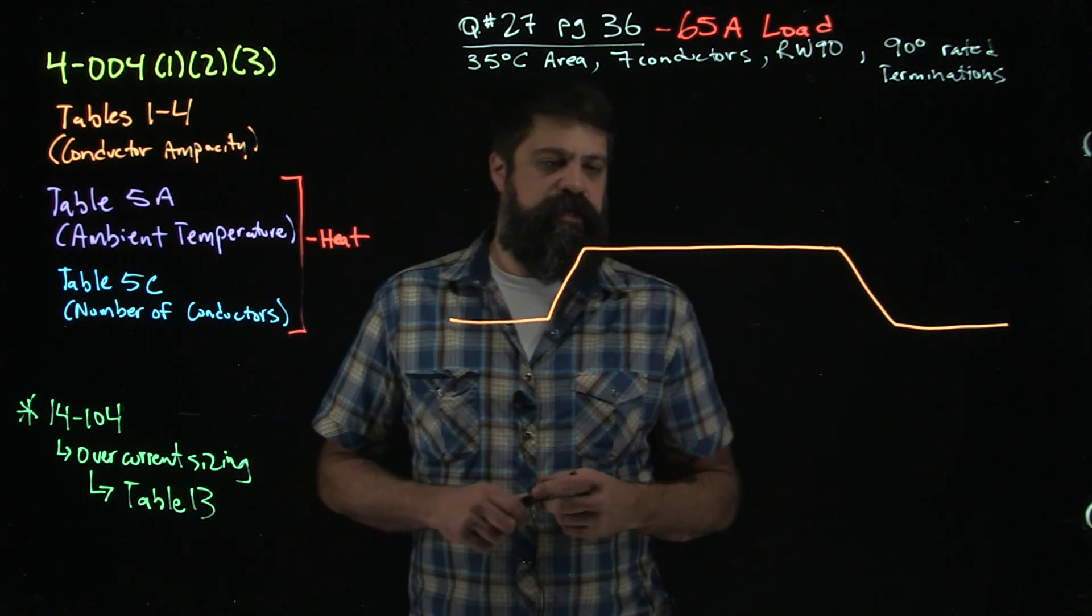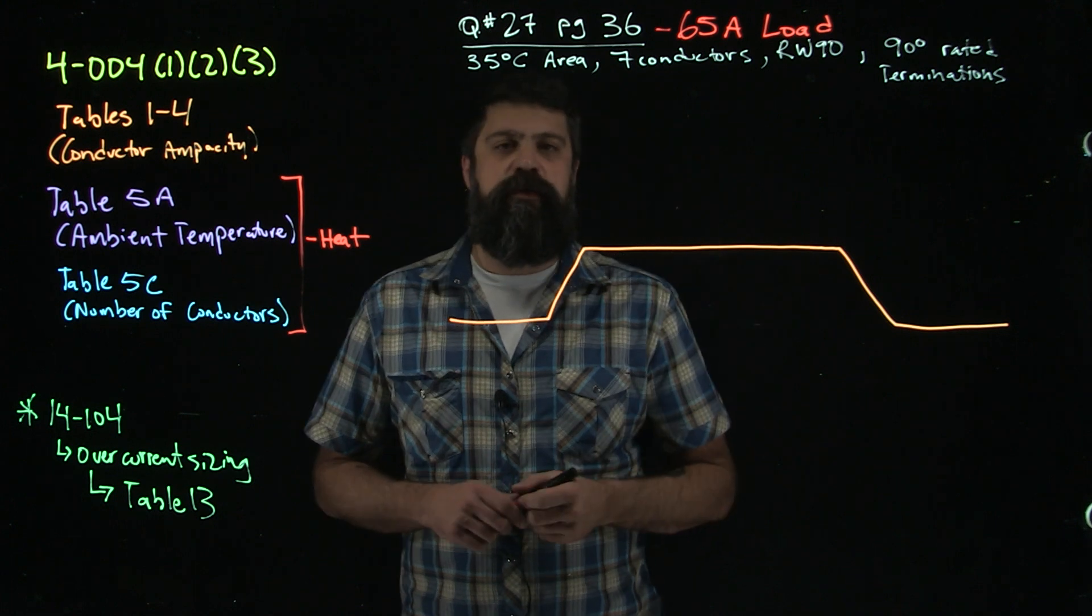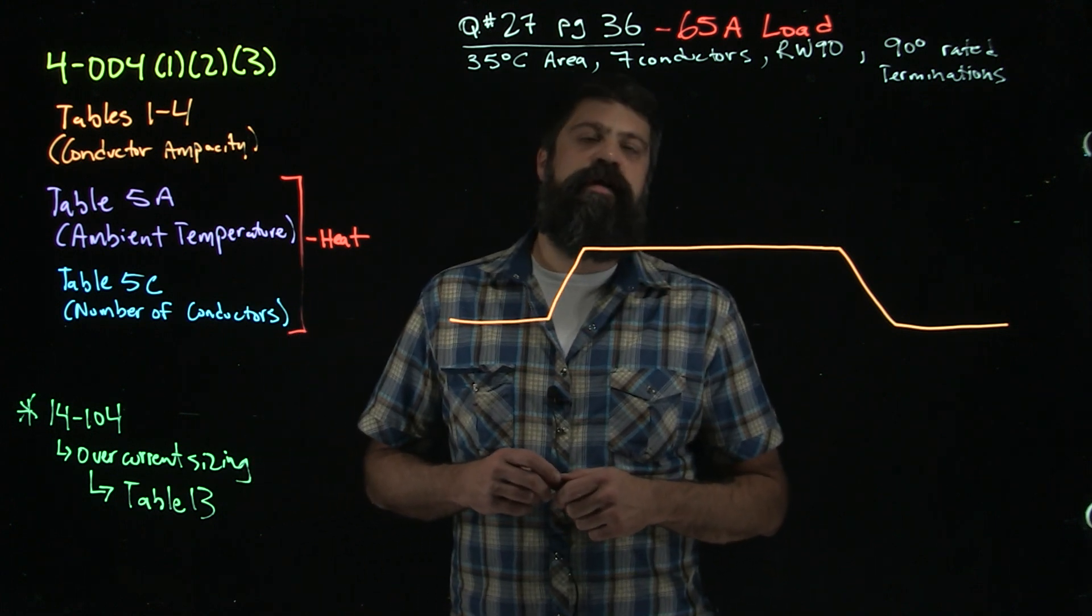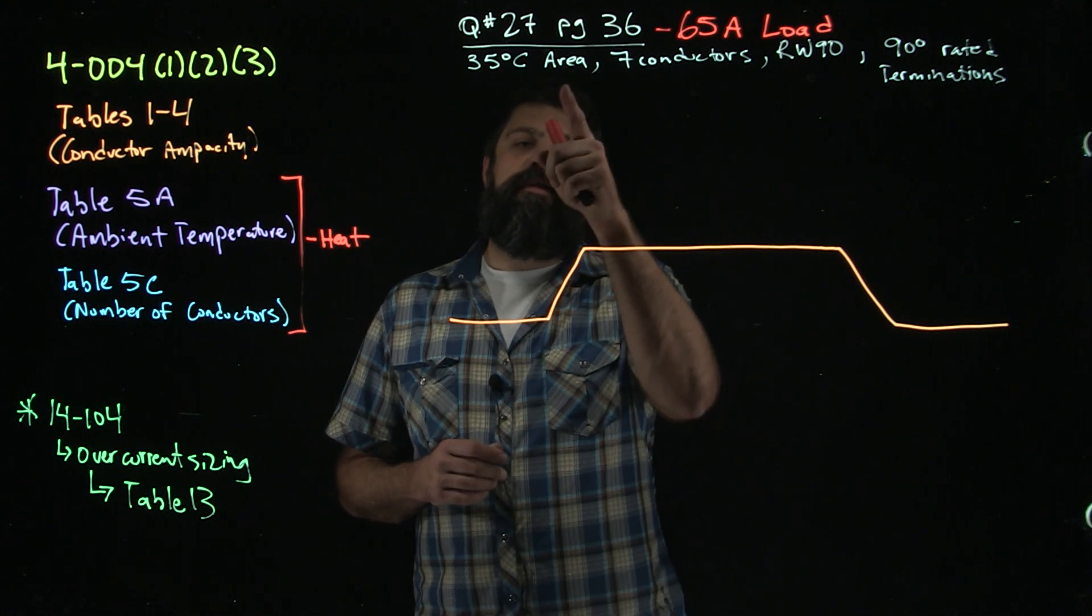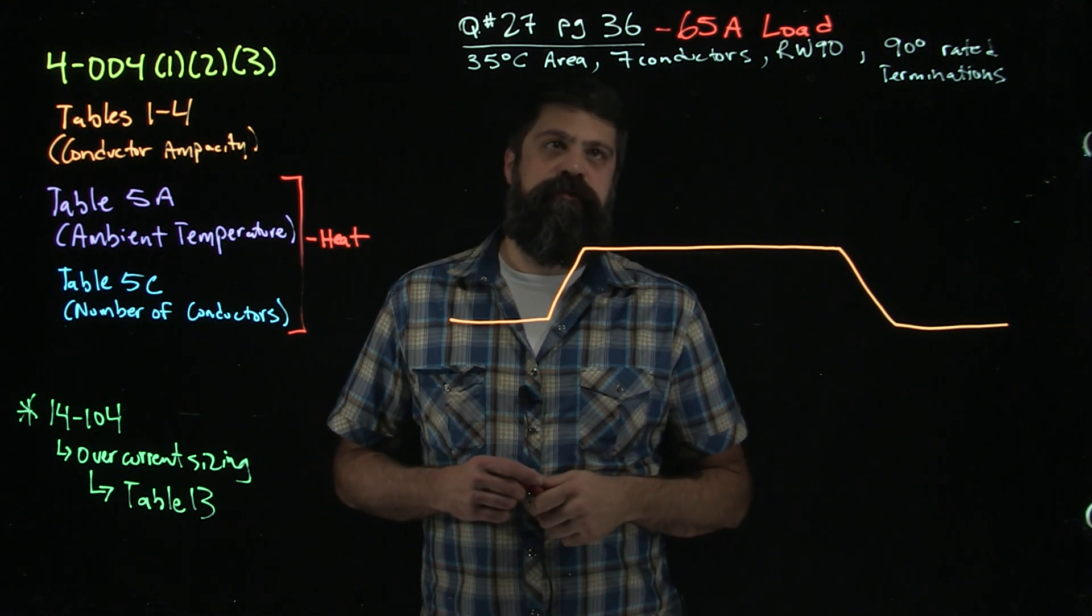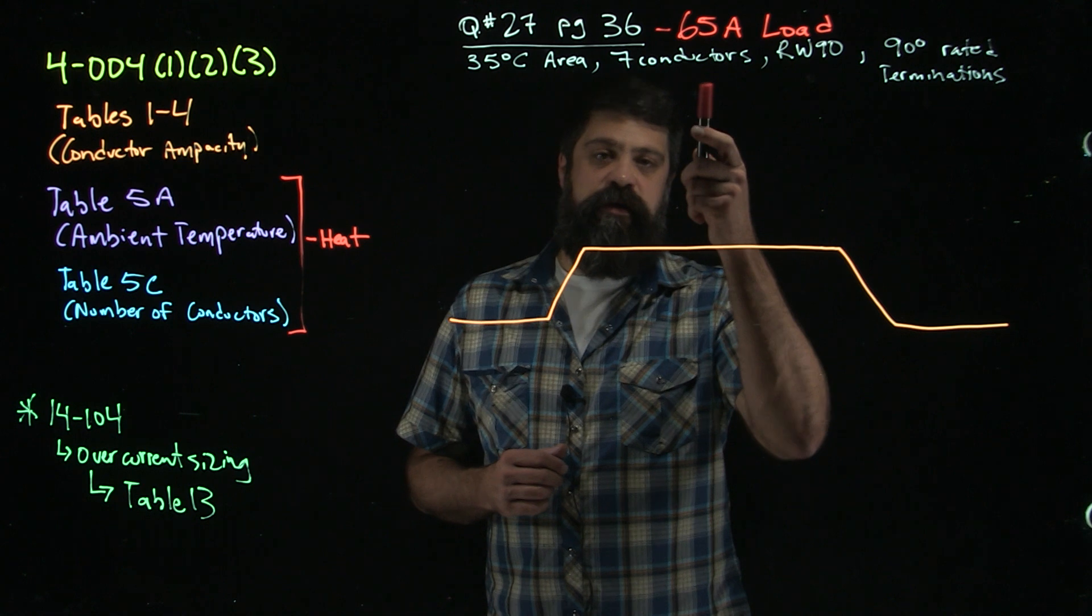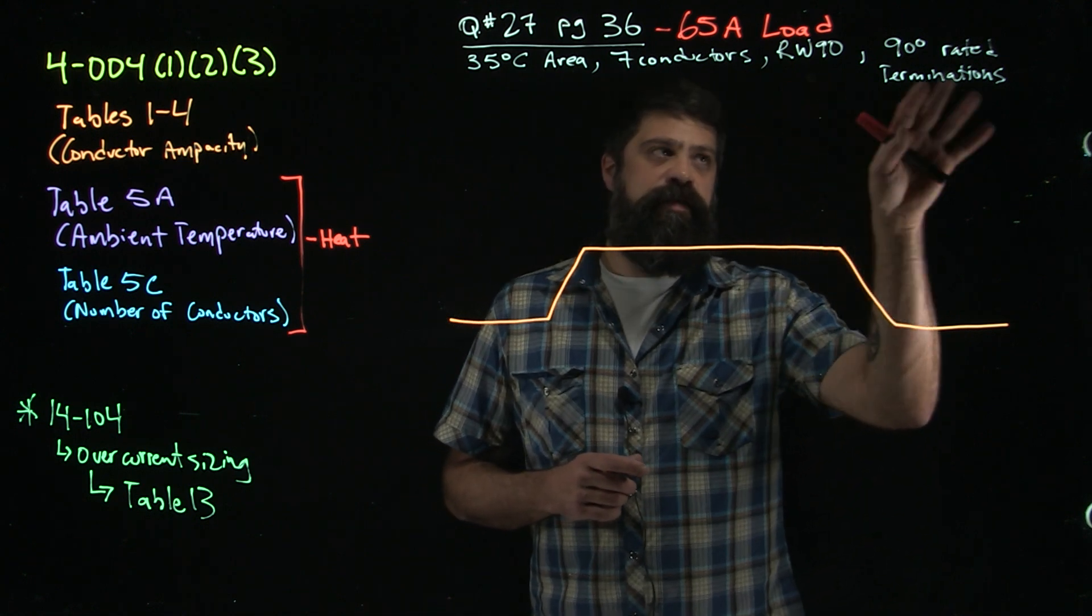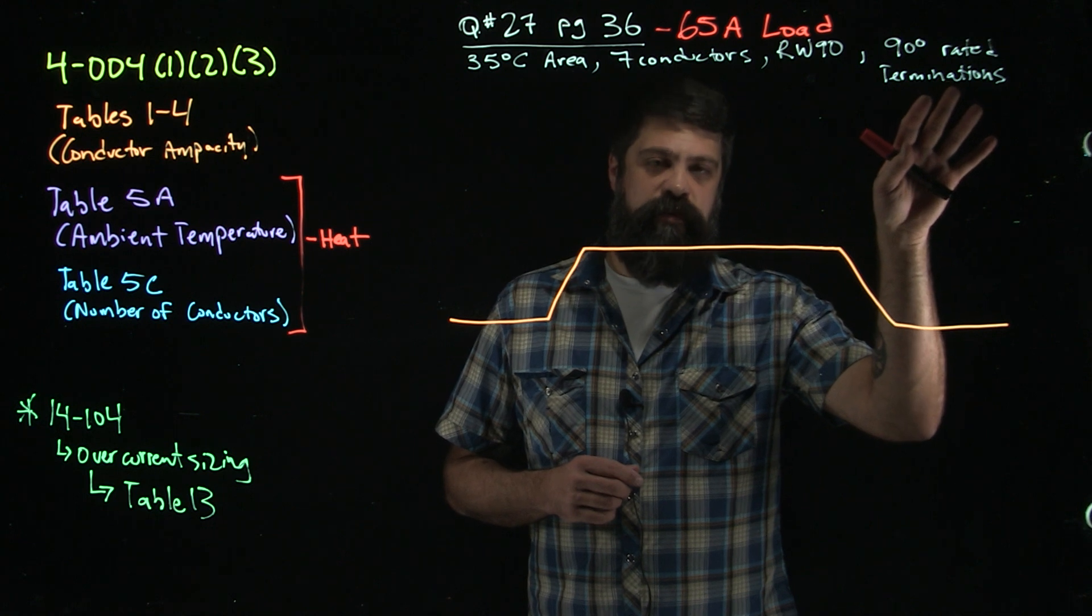We'll do the same thing as we did last time. This time we're going to be in question number 27 on page 36 of your workbook. We're going to start with a 65 amp load, but to get there we're going to have to go through an area that's 35 degrees. We're going to have seven conductors total inside of that conduit that's going to be run in RW90, and this time everything is 90 degree rated terminations.